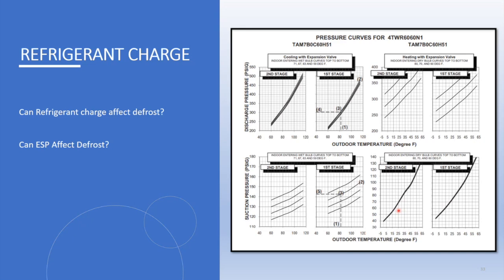I've seen it many times where we have really low refrigerant pressures, but then we do a few forced defrosts and now the pressures look good. So then we've got to look at something else. So don't adjust based on these. They're for reference only.